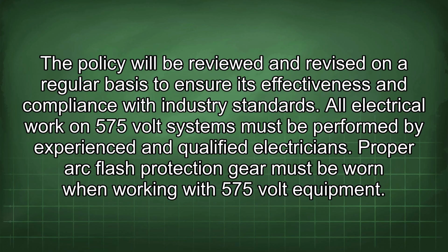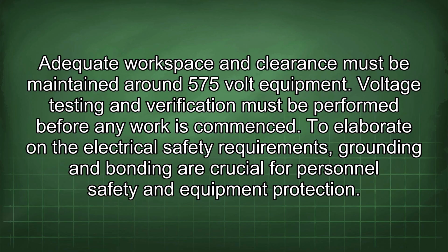All electrical work on 575-volt systems must be performed by experienced and qualified electricians. Proper arc flash protection gear must be worn when working with 575-volt equipment. Adequate workspace and clearance must be maintained around 575-volt equipment. Voltage testing and verification must be performed before any work is commenced.